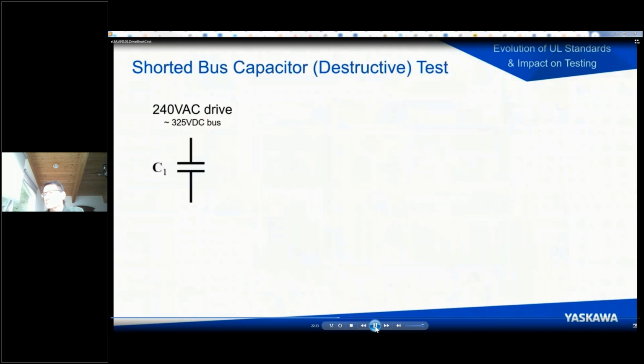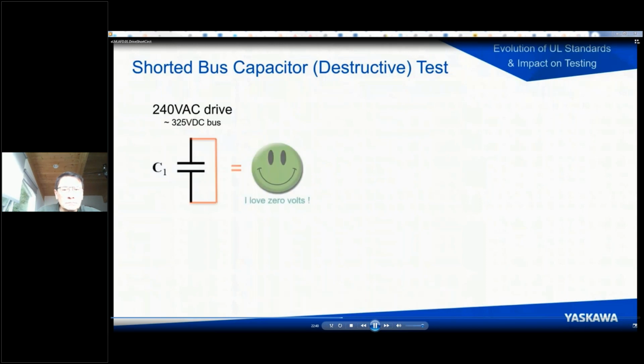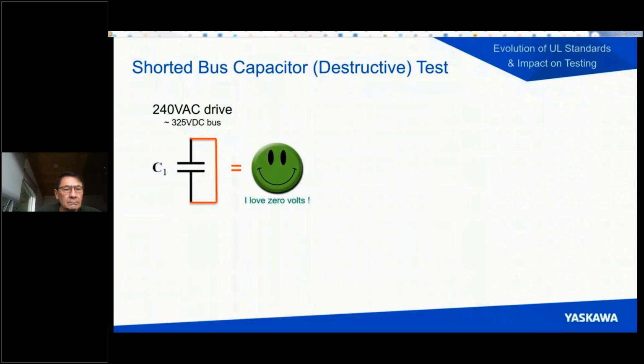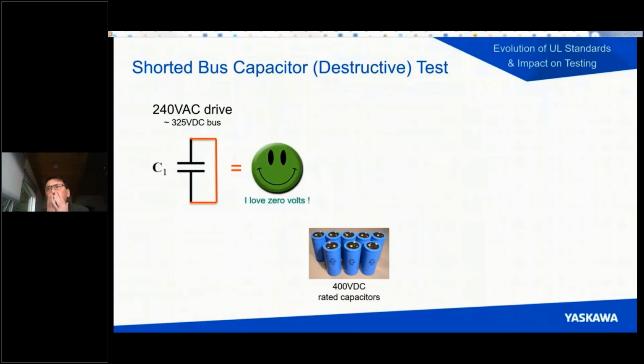So let's talk about the shorted bus capacitor test. Now normally on a 240 volt drive, the rectified value of that is nominally around 325 volts DC. So when we apply a short across that, as required by UL, the capacitor loves it. He says, I have 0 volts, I love it, no problem. Okay, now why is that? Because these are 400 volt rated capacitors, and certainly it has no issue with 325 volts, nor does it have an issue with 0 volts, right?